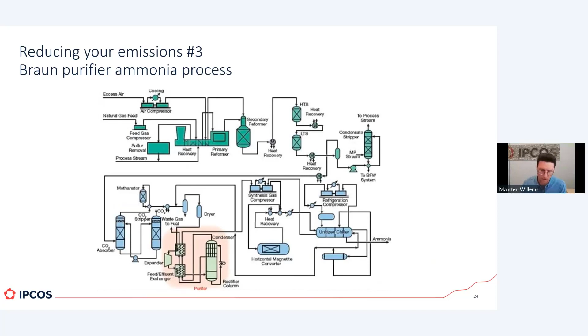Let me start at the bottom of your screen with the air-to-gas ratio. As you can already feel, in the ideal situation it would be a 1:3 ratio for NH3. But of course, the hydrogen that comes out of your reformers is not always the same. So for an operator, it's not always easy to control that, especially because there's that very big loop afterwards. If you change that air-to-gas ratio now, it will take maybe 6 hours before you see the effect of it within that big loop. So for an operator to do that manually, that's very difficult to control. That's what you see on the left.